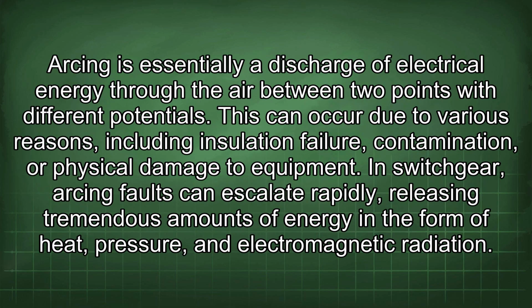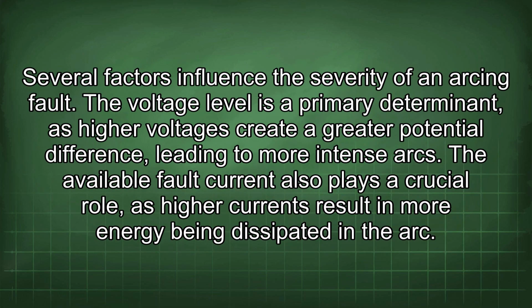Arcing is essentially a discharge of electrical energy through the air between 2 points with different potentials. This can occur due to various reasons, including insulation failure, contamination, or physical damage to equipment. In switchgear, arcing faults can escalate rapidly, releasing tremendous amounts of energy in the form of heat, pressure, and electromagnetic radiation. Several factors influence the severity of an arcing fault.